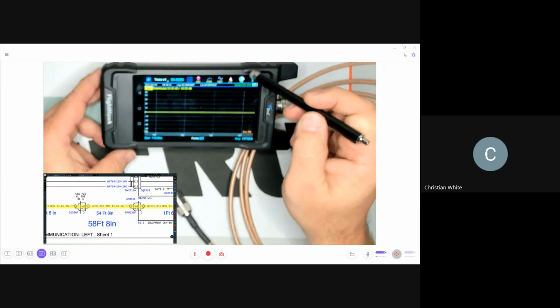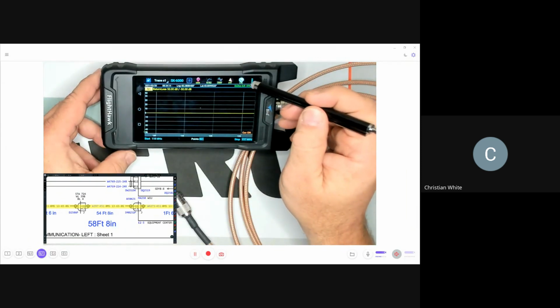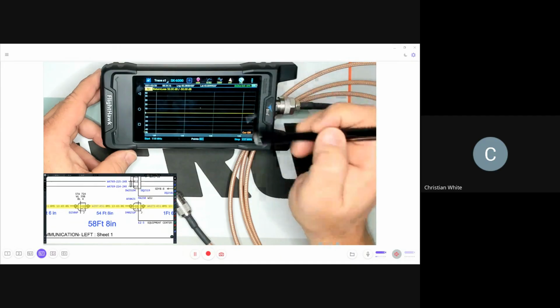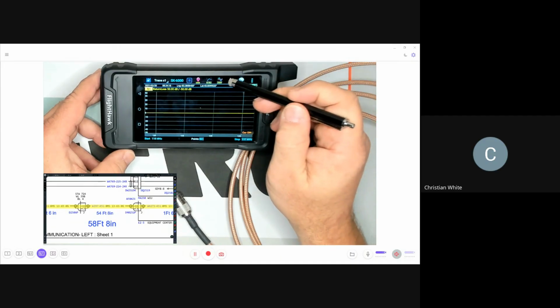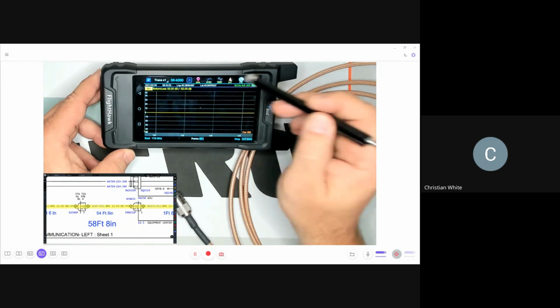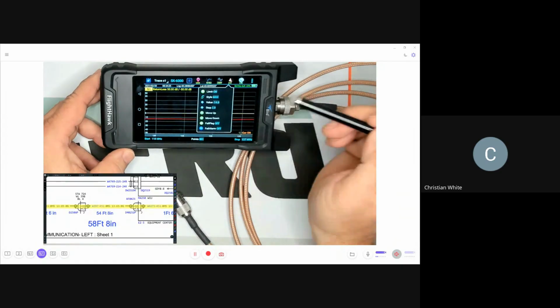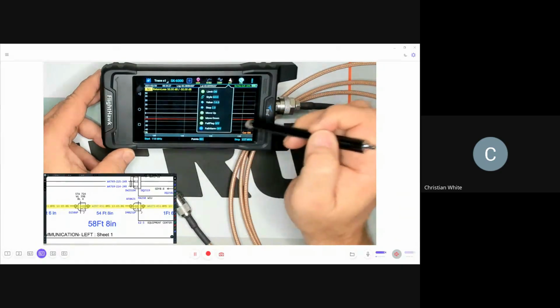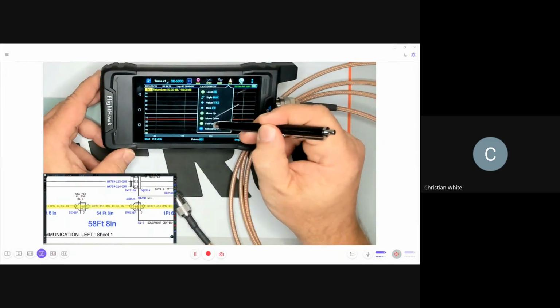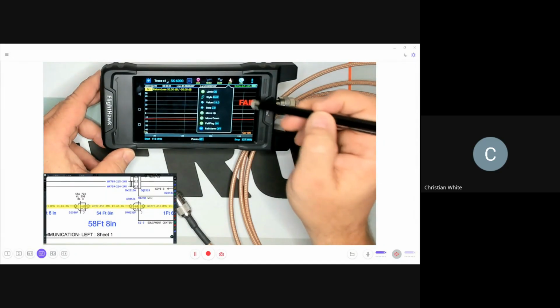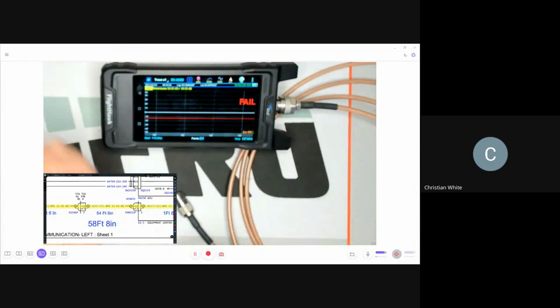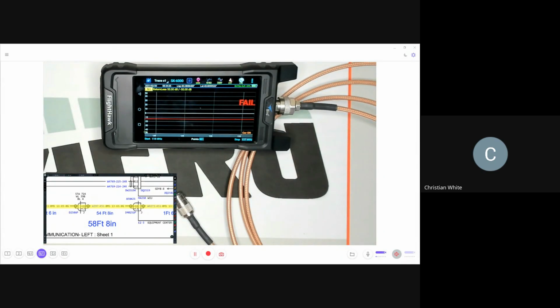So we did our frequency, we calibrated after the frequency, we put our information in for distance default. Now we're going to turn our limit on. It's going to give us our limit line, which is this red line, and we're also going to turn our fail flag on. That makes it really, really simple. This is the hardest part - after you do it a few times, you can go through and do this pretty quickly. This is the hardest part of using this whole thing, doing the setup.